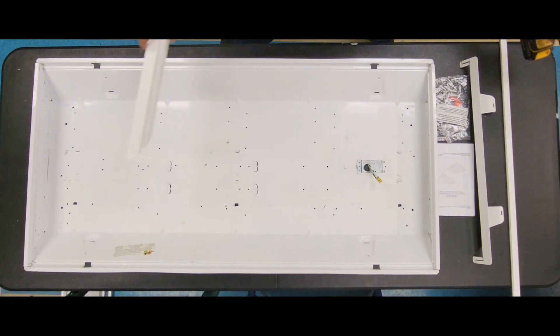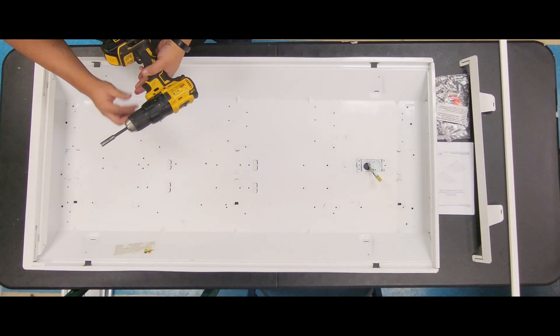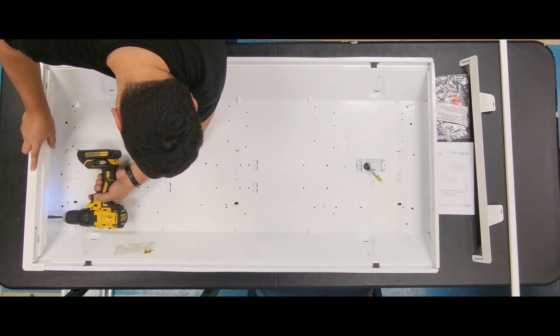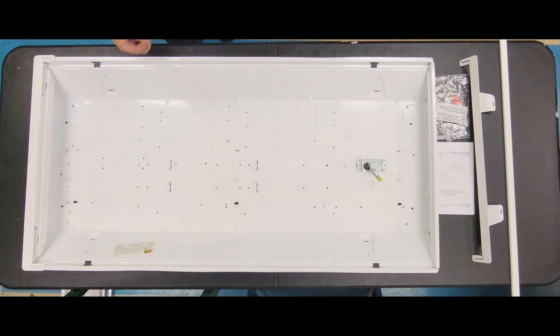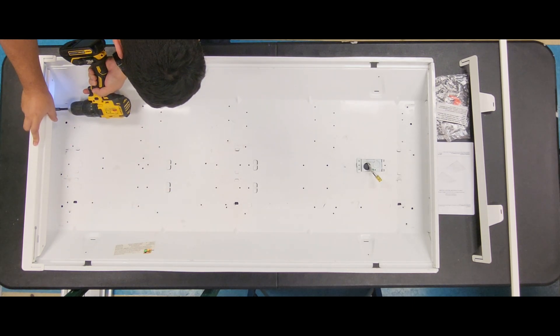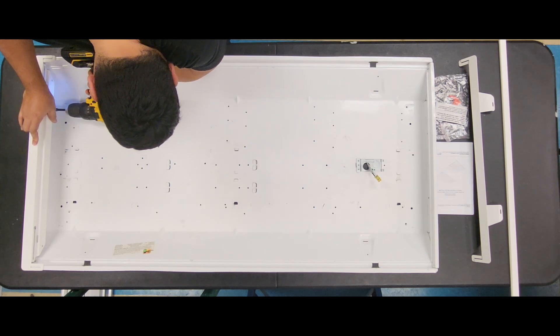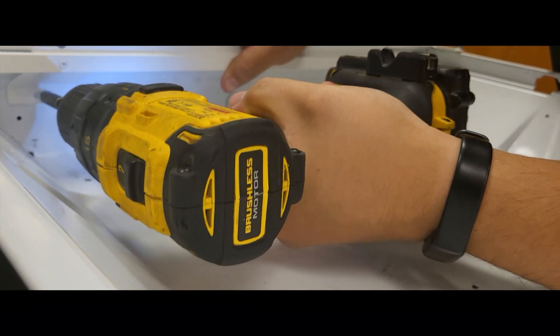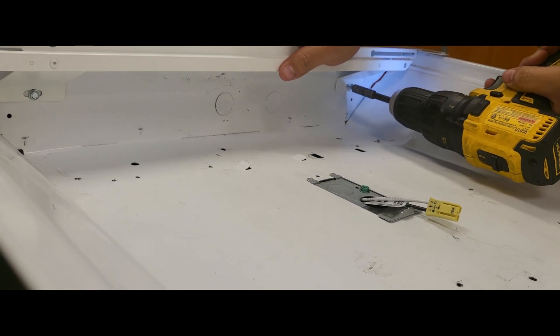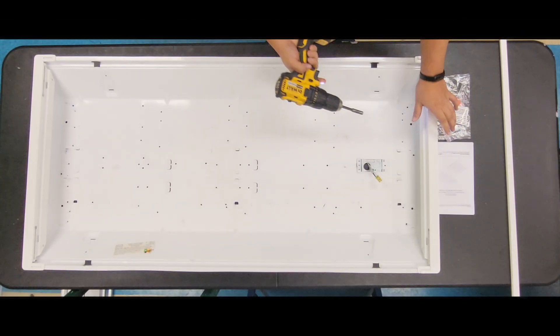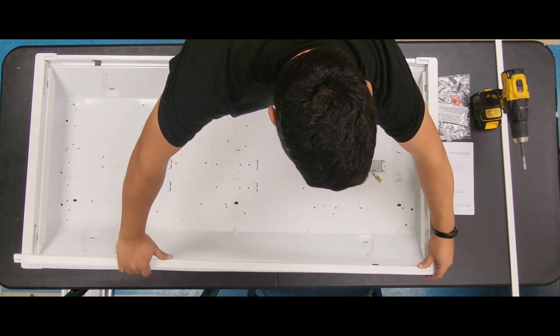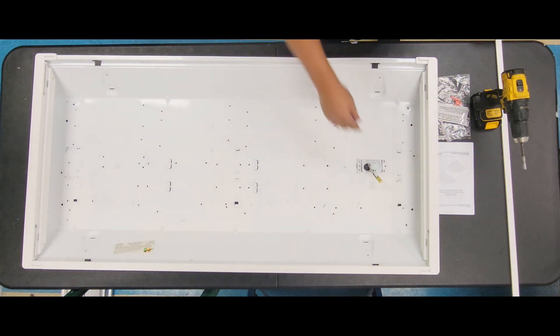Next, we're going to start the installation process of our retrofit kit by installing the end brackets. These are going to be mounted on the ends of the luminaire using the self-tapping screws provided in the hardware bag. Once those end brackets are installed, the side mounting brackets can be installed by clipping the side tabs into the end bracket slots.